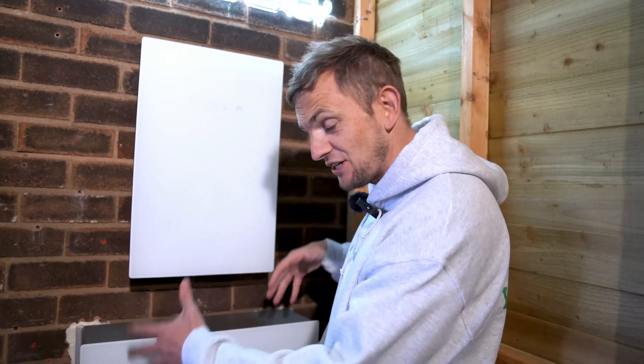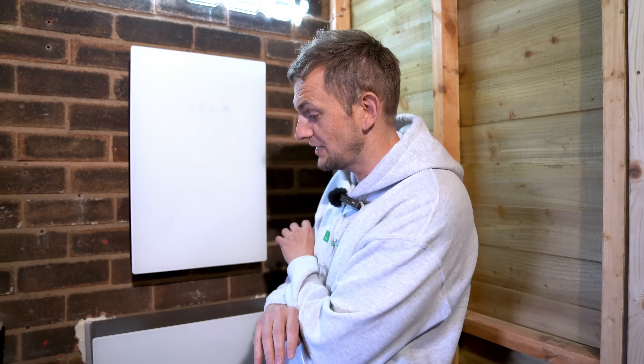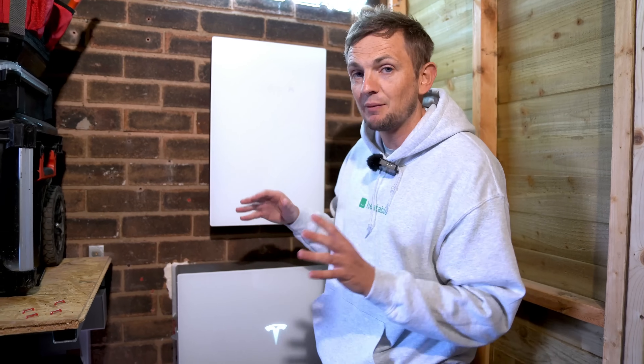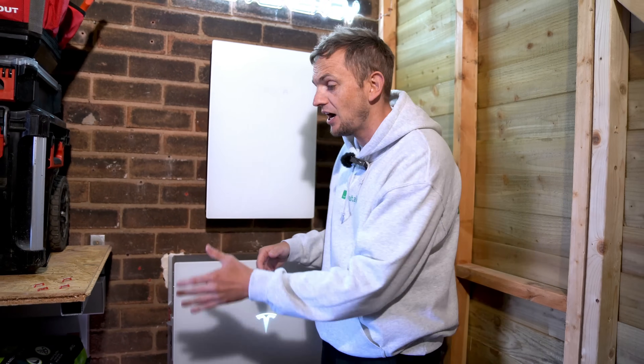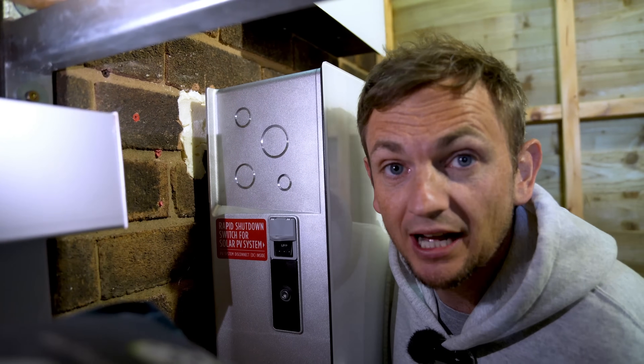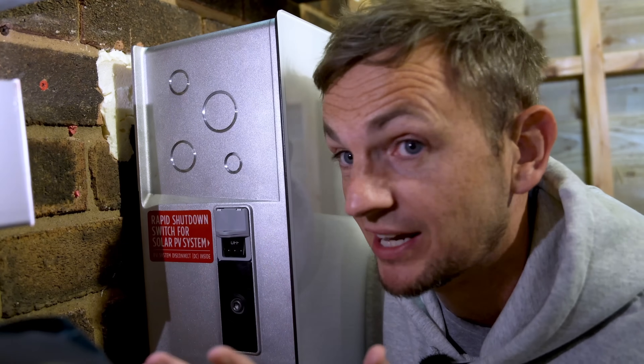First inspection of this product — it looks like a dummy unit because where are all the cables? That's because Powerwall 3s have multiple cable entry options. This one has been rear cable entry, which makes it look super slick and clean. However, if you haven't got that luxury, there are options for side cable entry. There are side entry knockouts in every size for different cable glands — just get a hammer, knock one out, and it flies straight out, nice and easy.